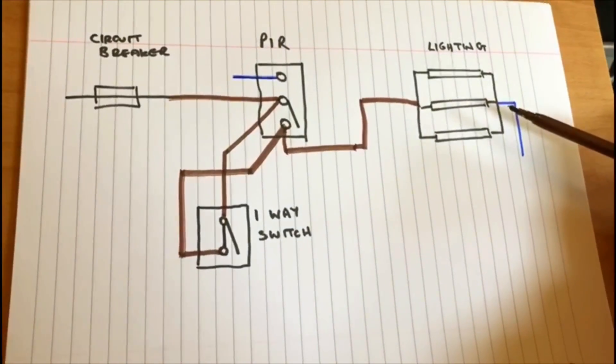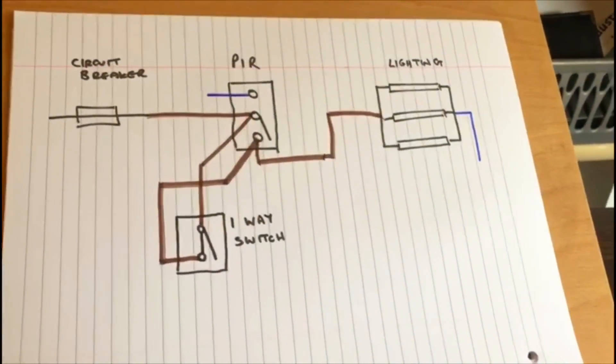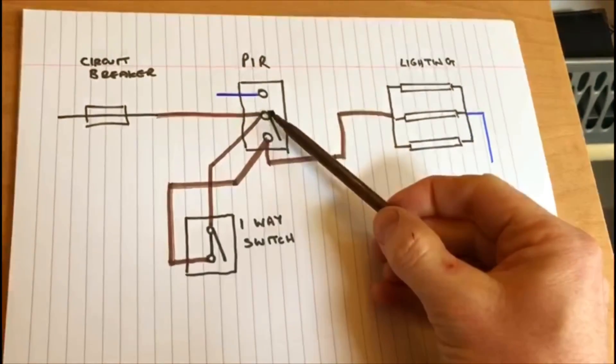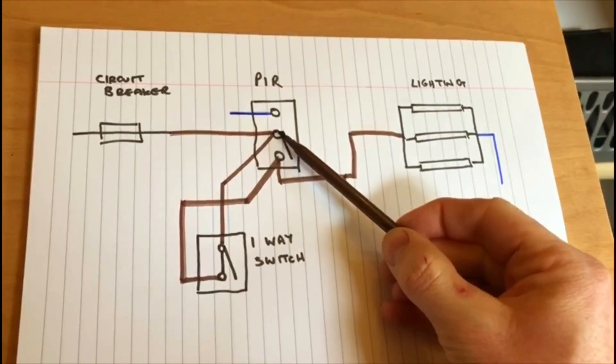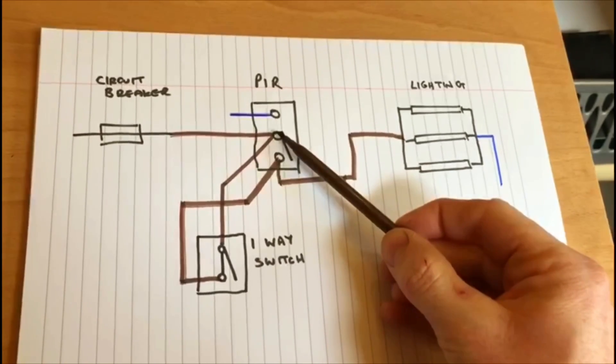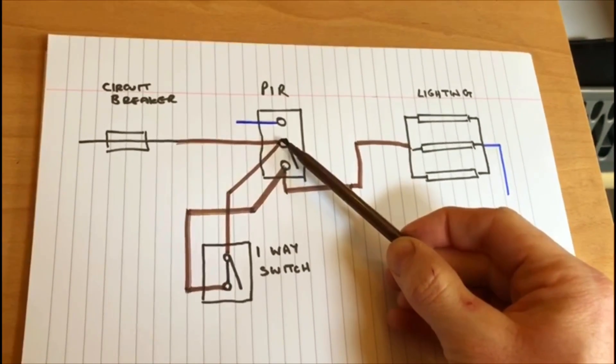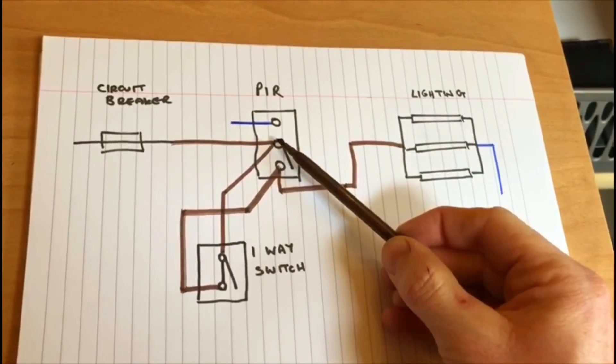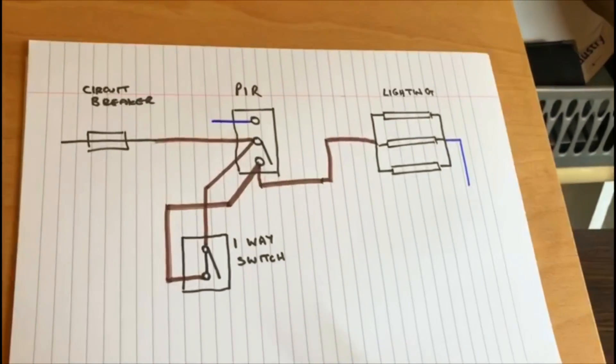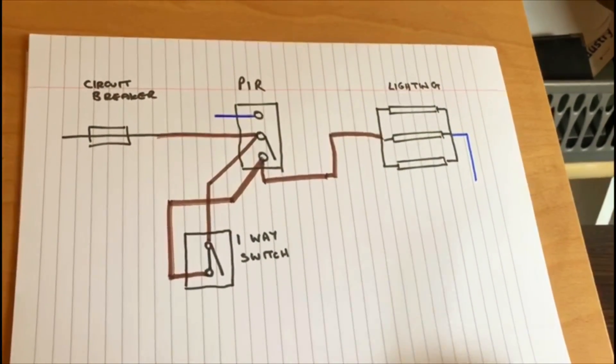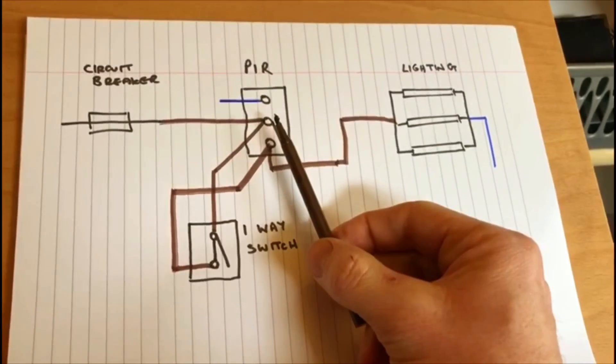And so that's relatively quite simple. Notice that we always have a permanent live supply going to the PIR. It's important that the PIR always has a permanent live supply going to it. You never want to switch the permanent live supply. The reason being is that these have got various electronic equipment inside that needs to be reset sometimes. So if you keep cutting the power to the PIR, that will cause various issues.